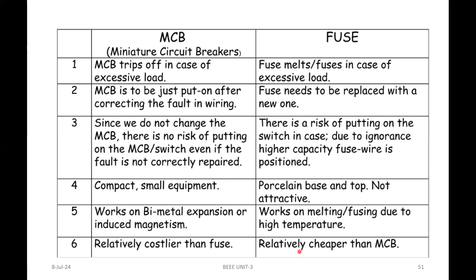It's just a compact and small equipment. A fuse has a porcelain base and top, not attractive. The MCB works on bimetal expansion or induced magnetism, that is solenoid or bimetallic strip, with the help of copper and steel. A fuse works on melting and fusing due to high temperature. Relatively, it's cheaper than an MCB. These are the different differentiations between MCB and fuse.